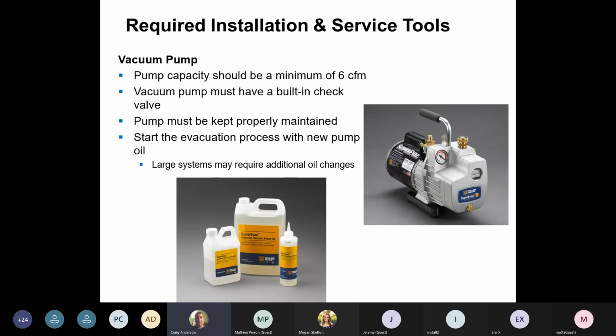Make sure you're changing the oil regularly. I'm not saying change it every time you use the unit, but change it regularly. On new installs, not too bad. We're dealing with new copper. We're only dealing with new equipment. If you're doing a lot of retrofits, you'll notice your vacuums take longer. It's taking longer to take the moisture out.